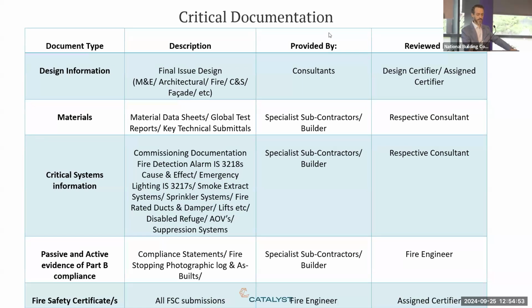Fire rated ducting, dampers - if they're fire dampers, are they normally open or normally closed? Some more complicated systems have normally closed dampers that need to open. That all needs to be captured in the cause and effect. It needs to be obvious to the building owner when they manage the system how they're going to actually maintain it and check it on an ongoing basis.